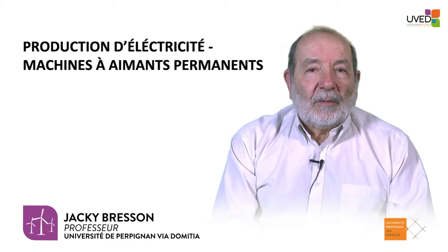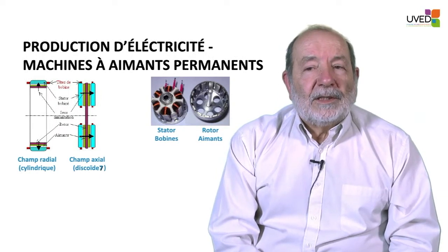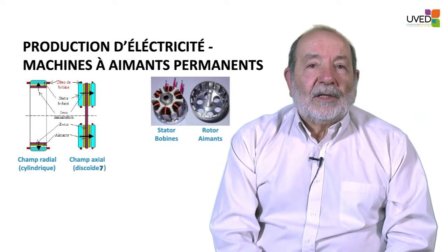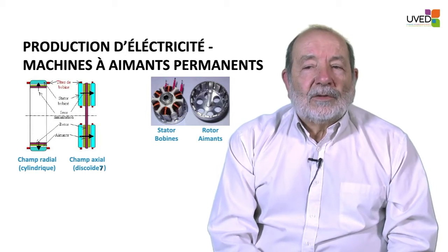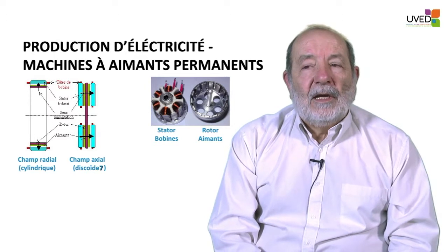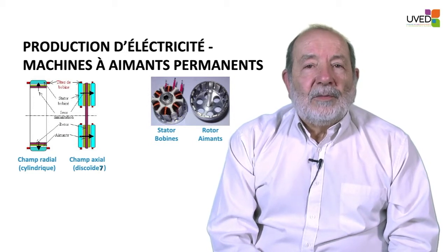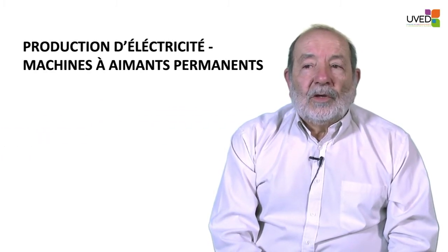The machines currently used are synchronous machines or permanent magnet motors — brushless motors. They use magnets that rotate in front of a coil. There are two categories: when the magnetic field is perpendicular to the rotating axis, we call it a radial or cylindrical machine; when the magnetic field is parallel to the rotating axis, we talk about discoid axial machines. The picture in the middle shows the elements fixed inside the rotor on which the blades are mounted, with magnets rotating in front of the coil attached to the stator.